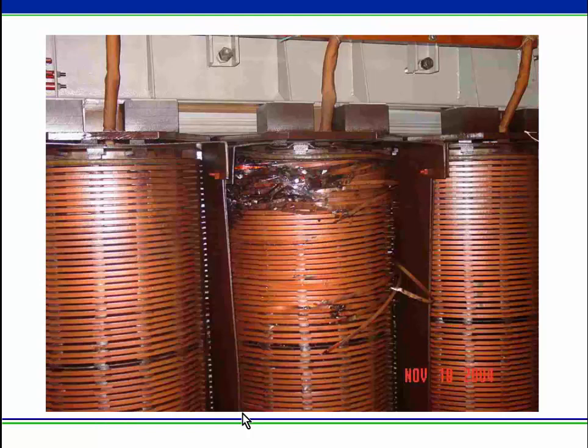Here's a picture of the inside of a three-phase power transformer. This power transformer used to be installed at a substation. So here are the three phases, and the way these are built, the secondary is wound first. You can't really see that, it's on the inside, and then the primary is wound on the outside, and those three coils are connected delta-Y typically for power transformers. That's a very common arrangement, not the only one, but a common one. And this one had a fault and blew apart.